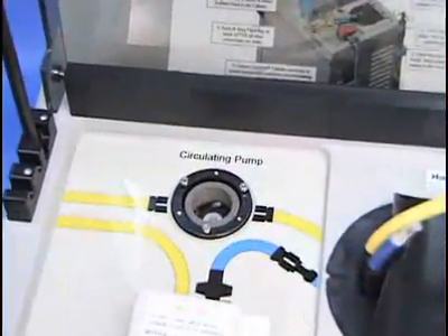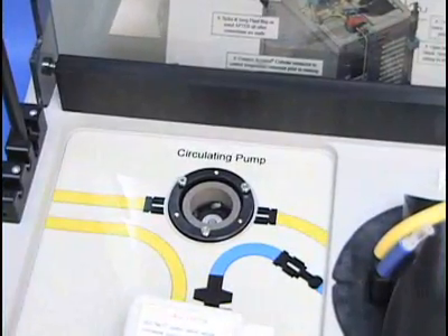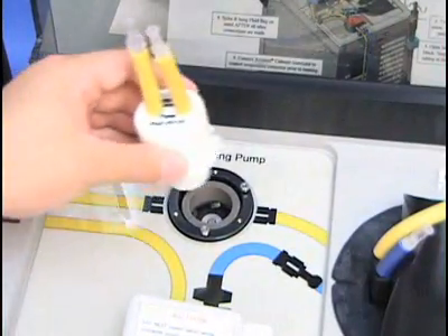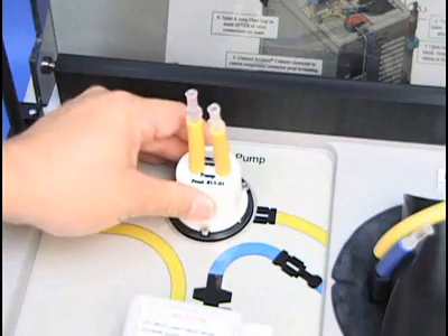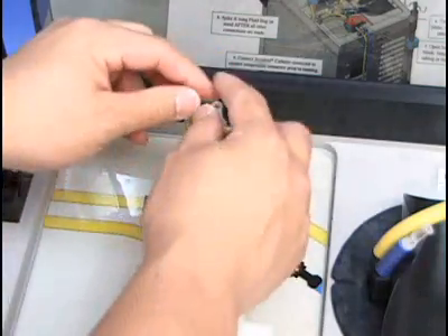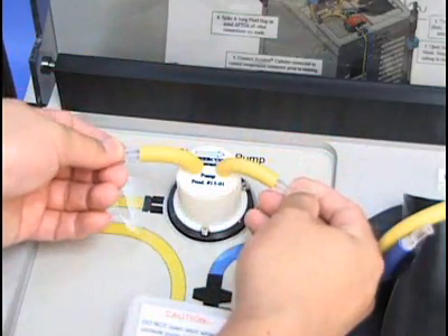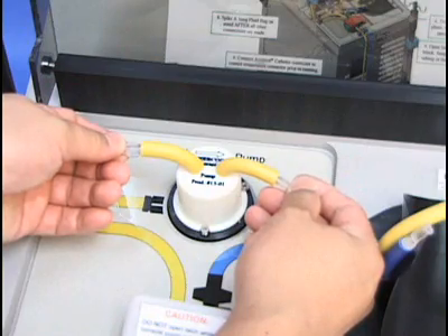Next, place the circulating pump where designated. The pump is magnetized and should lock right into place. Note that it must be installed so the arrow is pointing toward the heat exchanger, or in the direction of flow. The connection tubes will then line up with the installation diagram.